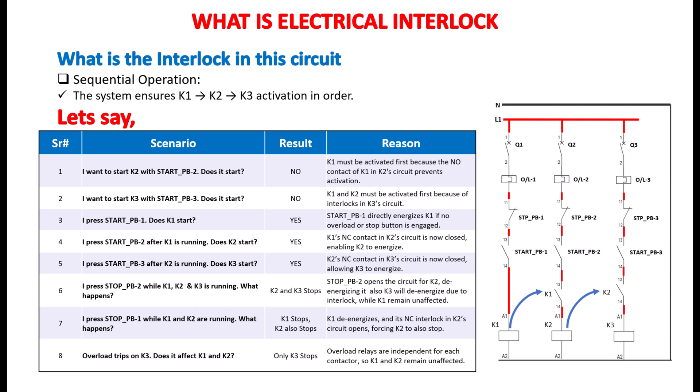Scenario 6. What happens if I press STOP PB2 while K1, K2, and K3 are running? K2 and K3 stop. The STOP button breaks K2's circuit, de-energizing it, and it also stops K3 as the K2 interlock is used there, but K1 remains unaffected.